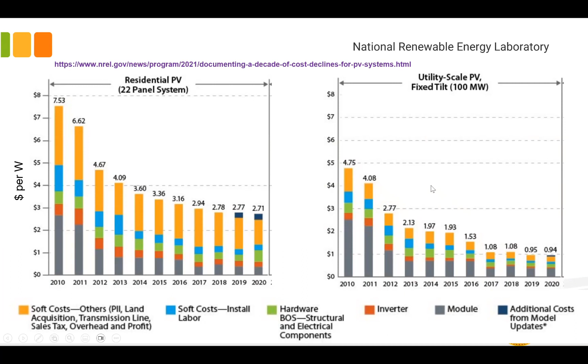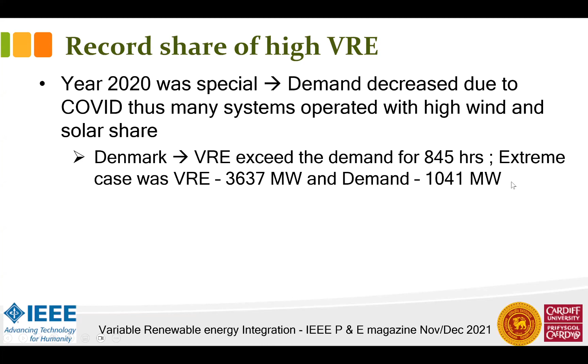Another thing we've noticed is during the COVID period, because demand was suppressed in many countries, we've seen many countries operating with a high share of renewables. For example, Denmark operated where variable renewable energy (VRE), which is solar and wind, exceeded demand for 845 hours, roughly 1/10 of the year. The extreme case was generation of 3,600 whereas demand was nearly 1,000, so more than 3 times the generation was available from VREs.